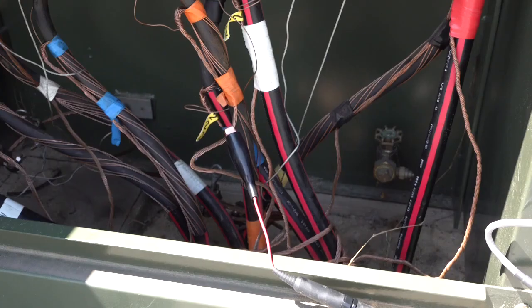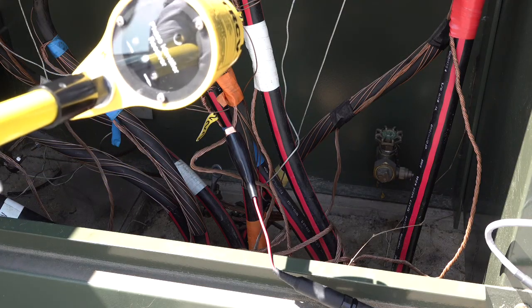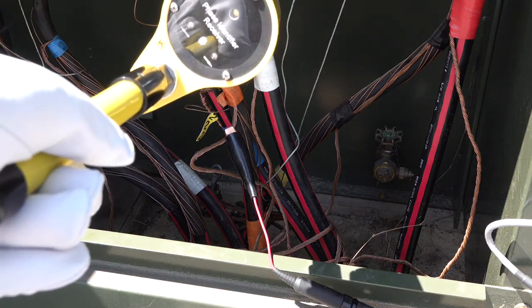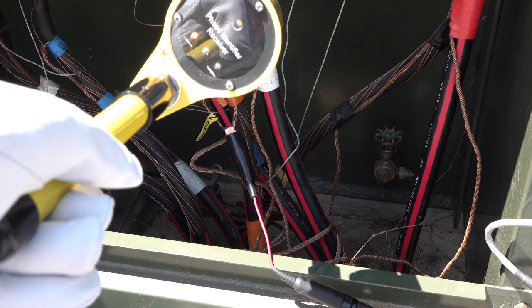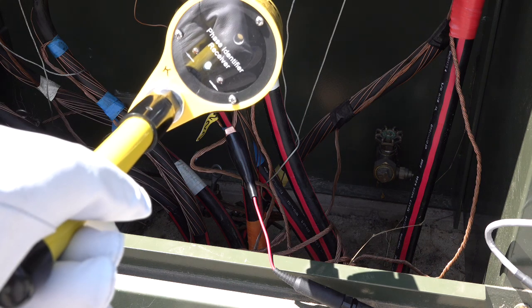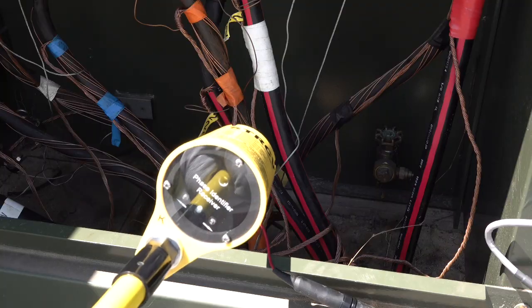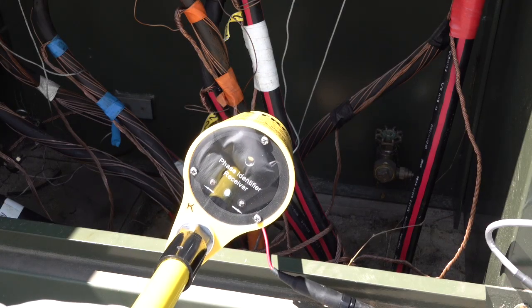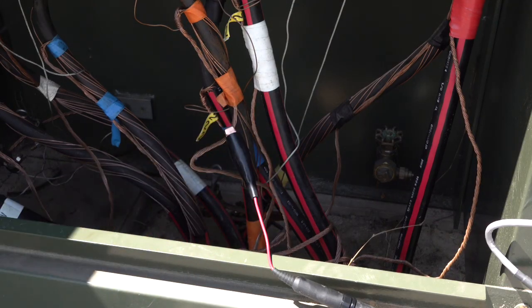Before leaving the near end to identify the de-energized primary cable in a manhole or a ditch, verify correct operation. Notice by testing the concentric above where the red lead is attached, we have an arrow pointing up or away from the ST800. If we were attached the black lead at this location, the arrow would be pointing down or back towards the ST800. And by testing on the opposite side of our red clamp, we should get an opposite arrow, so it's pointing down towards the ground.